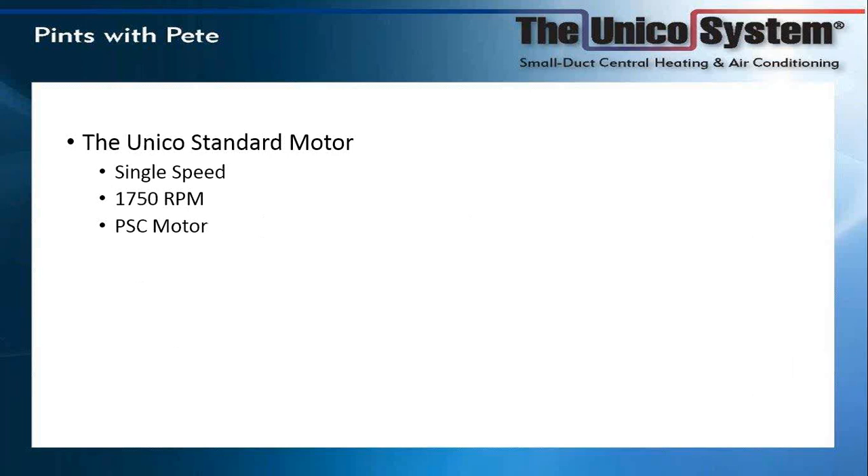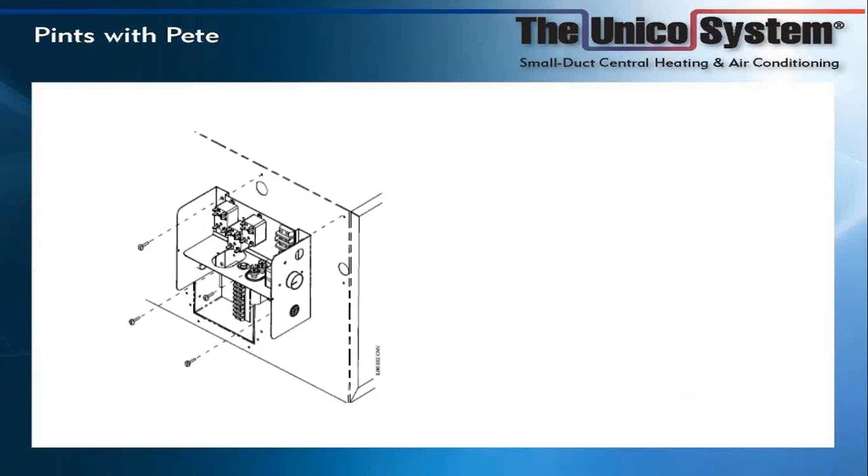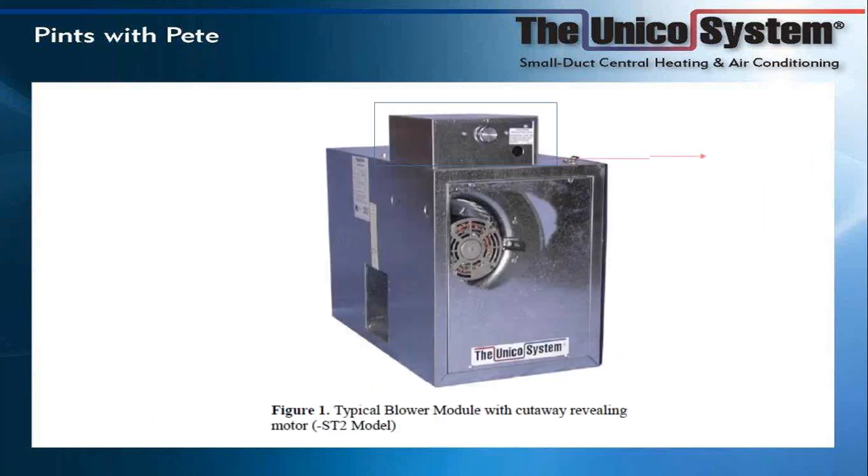The first one we have is our standard motor, the ST2. This is a single-speed, 1750 RPM, 240-volt PSC motor. A lot of people in customer service told me that many are not aware of this rheostat — here's a picture of it. This board can be mounted on the top or side of the blower module.